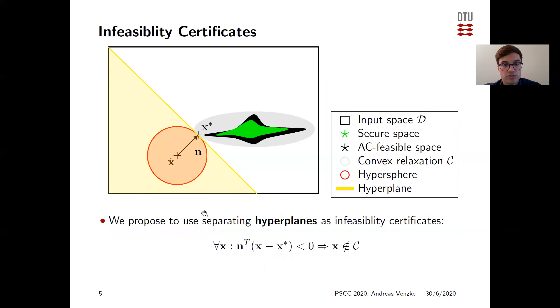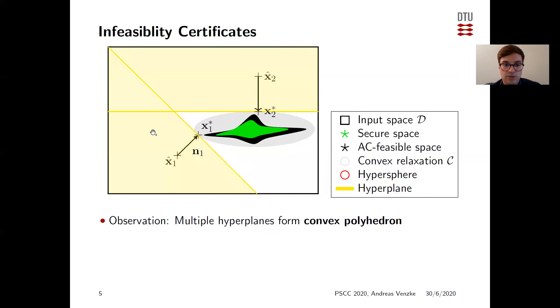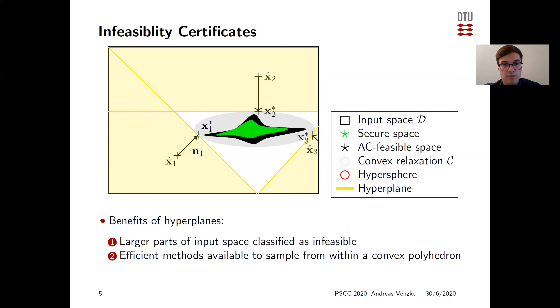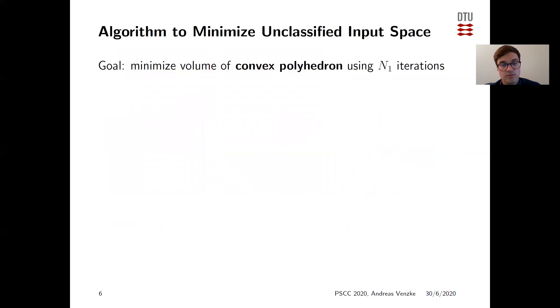Here we propose to use separating hyperplanes as infeasibility certificates instead. All operating points on one side of the hyperplane are guaranteed to be not secure. Using multiple hyperplanes, these form a convex polyhedron, so the unclassified input space is characterized by a convex polyhedron. The benefit of hyperplanes over hyperspheres is that larger parts of the input space are classified as infeasible, and we have efficient methods to sample from within the convex polyhedron. Based on these insights, we propose an algorithm to minimize the unclassified input space — equivalently minimizing the volume of the convex polyhedron — up to an upper number of N1 iterations.